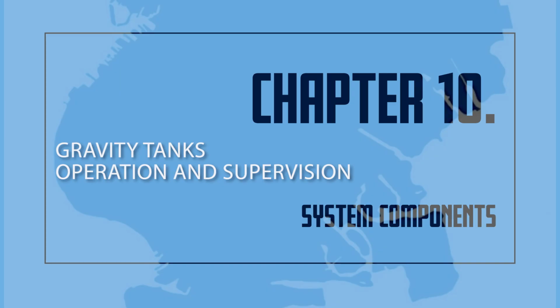Operation and supervision. When fire pumps are activated by electric automatic controllers, it is essential that they are constantly monitored to ensure the availability of the electrical power supply in case of an emergency. For this reason, supervisory devices are installed on the pumps to alert the certificate of fitness holder and/or a central monitoring station when there is an electrical power failure. In cases where steam turbines or internal combustion engines are used, similar supervisory devices are installed to signal when there is a problem with the controlling equipment.